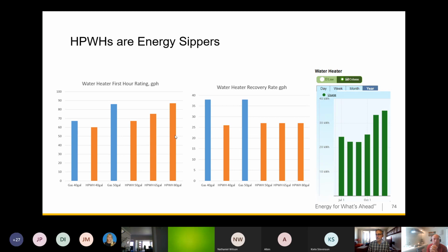And Nick, in relation to the upsizing, and we started to have this conversation, but I don't want to make it lengthy. Could you avoid going to an 80-gallon by increasing the temperature to 140 degrees and then putting in an anti-scald valve? Mixing valves, sure. Yeah, I've tried to keep this simple for early adopters to go to their plumber and say, hey, I want an 80-gallon. But absolutely, you can have a higher temperature set point with mixing valves at the unit. This is how the 120-volt units are mostly designed. So that increases capacity because you're storing more heat in the tank and mixing it with cold water on the way out of the tank. Yeah, that's another good solution. Yep. It's less expensive to do it that way, and we run ours that way. And so it's an alternative if in fact you can't fit an 80-gallon in your space for a reason. So I just want to make sure people see options as well.